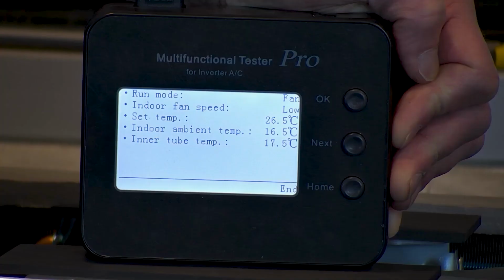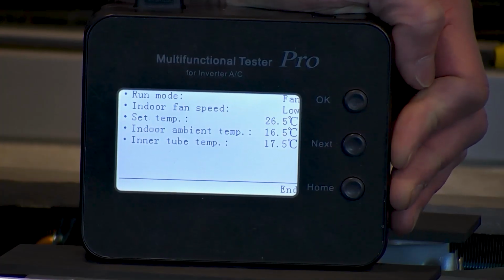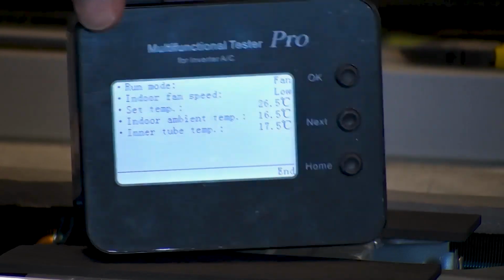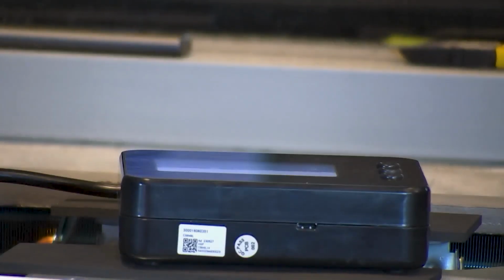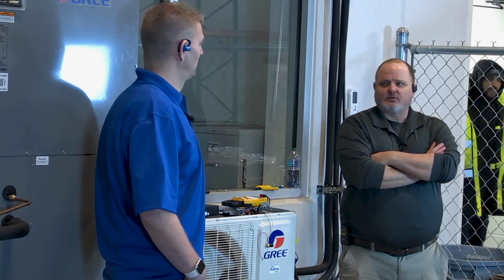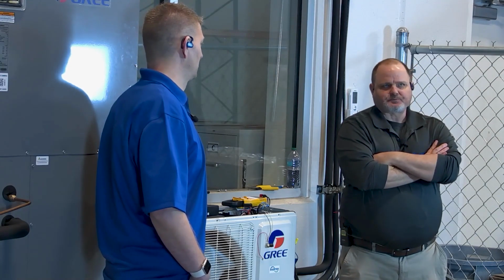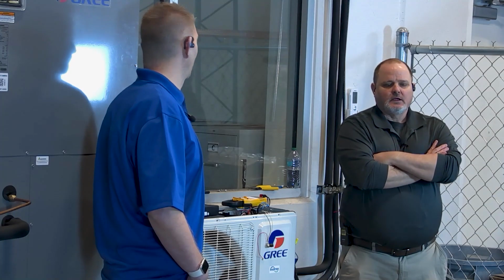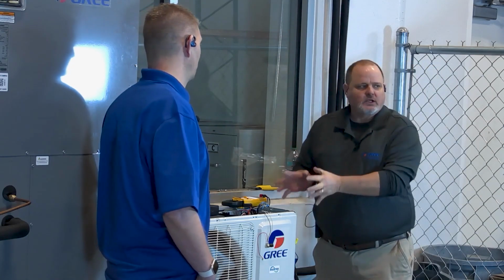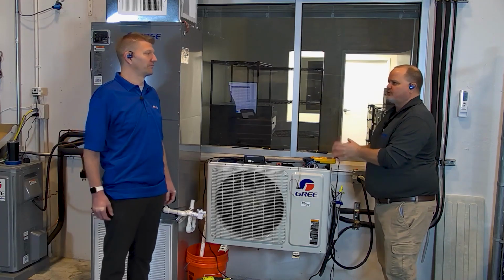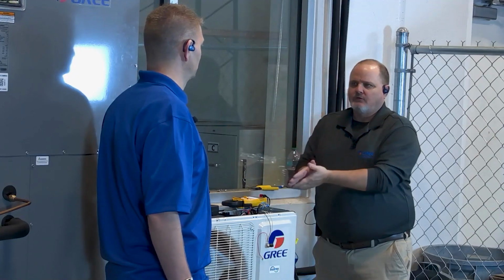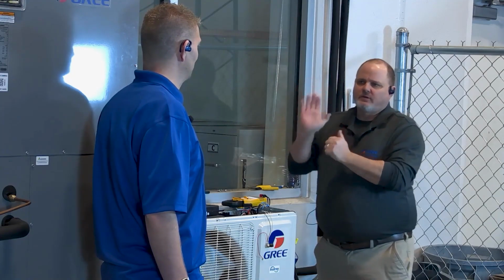Now, let's say you're out on the job, and you've got an E6 error code. On the E6 error code, we simulate the outdoor unit runs. We know the problem's not there. Then we simulate the indoor unit, and we can't detect it. Again, you're starting outside. That's the easiest place for you to start. That way you can test both outdoor and indoor. But let's say it doesn't detect the indoor unit.